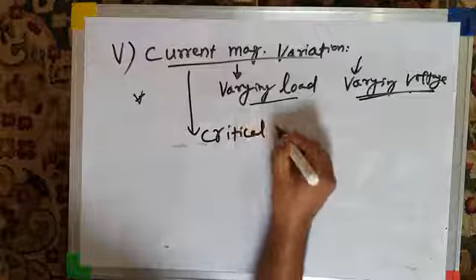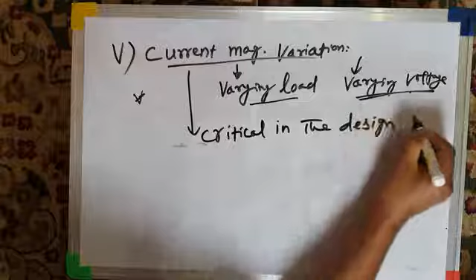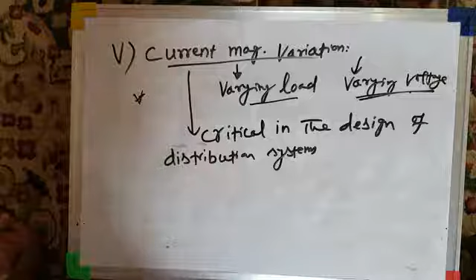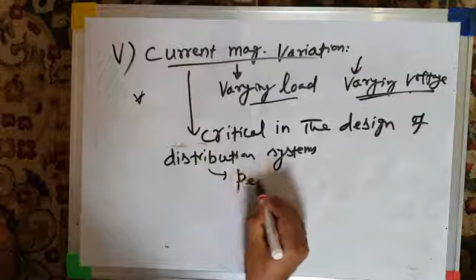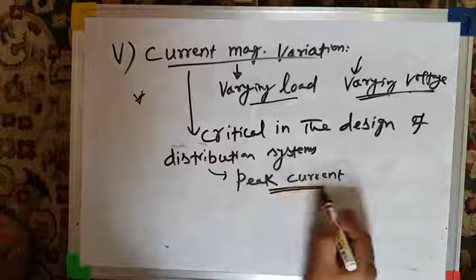And this current magnitude variation is very critical in the design of distribution systems. Whether your distribution system comprises transformer, conductors, and loads, it is mainly designed by the peak current, because your transformer must be able to bear the peak, or maximum, magnitude of current. So all components of the distribution system, whether transformer or lines or any other component, are designed for peak current. But the revenue of the utility is determined by average current. What is the average current taken by the load?